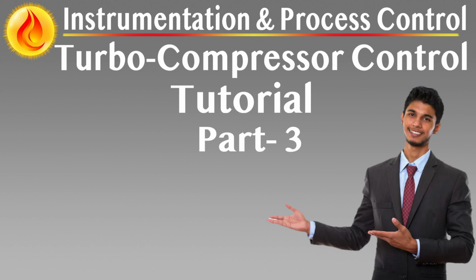Automatic duty standby management. Where redundant auxiliaries, e.g. dual lube oil pumps, are installed, the TCCS automatically initiates the standby unit upon failure of the duty unit, monitors health conditions such as motor status, trip signals, and flow confirmation, raises alarms upon switchover, and logs event history for analysis.